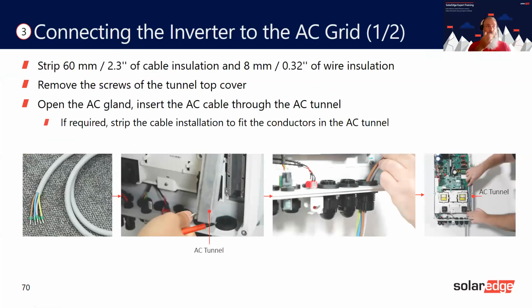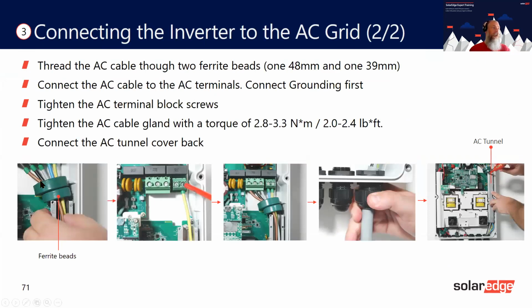So we've got a tunnel basically, which is this bit here. You pull this tunnel off, you run the AC cable through the tunnel, and you put the tunnel back on. It just secures it, makes it neater, stops it getting in the way in case it's pinched when putting the lid in place. Then you put the ferrite cores around it at the top. You terminate the cables as such, and you then put the tunnel back on, as you can see on here. And don't forget to tighten up the gland as well.